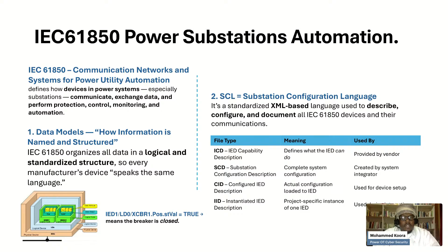In brief, that tells each IED, when it trips, which IED it should communicate with, and for which type of trip it will communicate with each different IED.